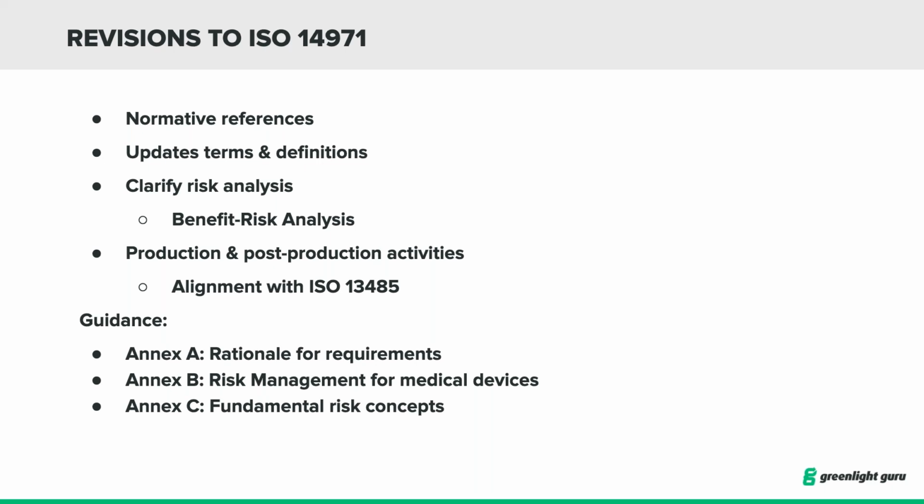And this is sort of the essence, if you will, of 14971, is you need to look not just at the failure states and conditions, but also the normal use cases and understand the situations that could lead to potential harm, and kind of wrap your head around that. But anyway, back to 14971 2019. A couple of updates.